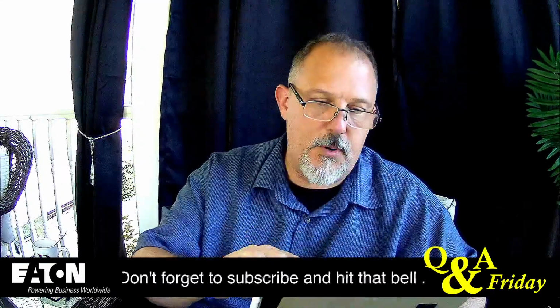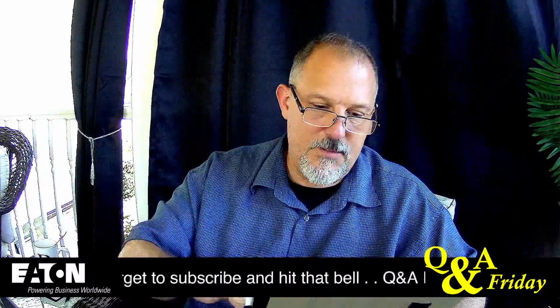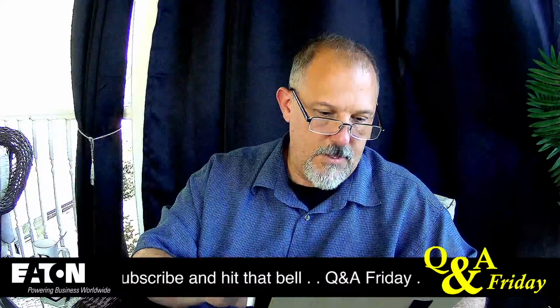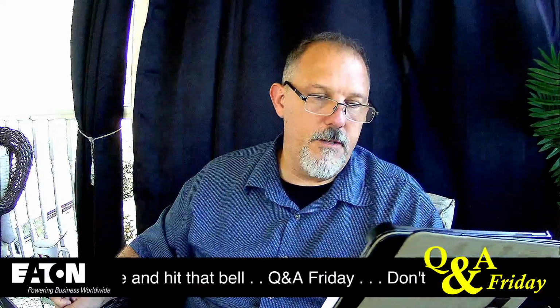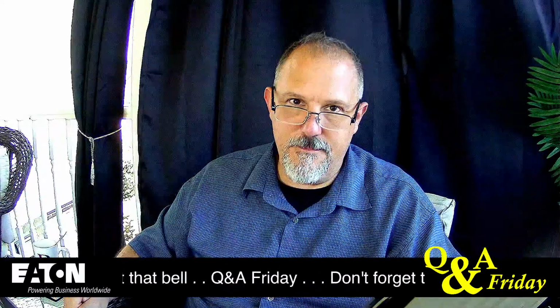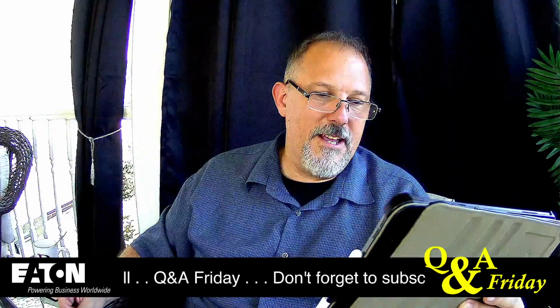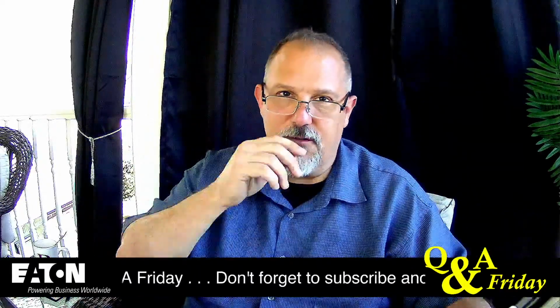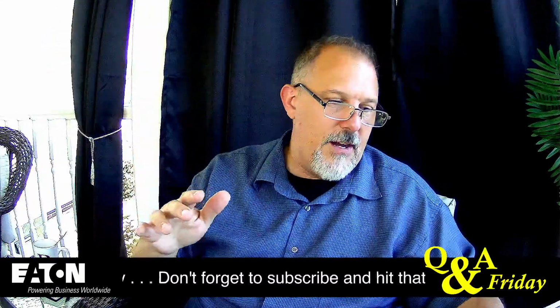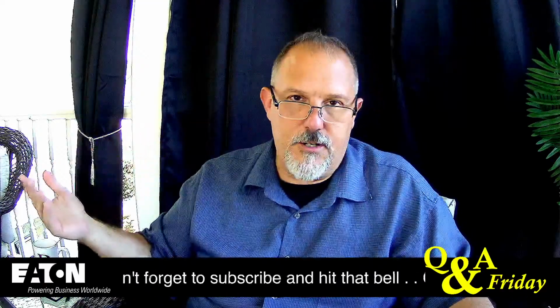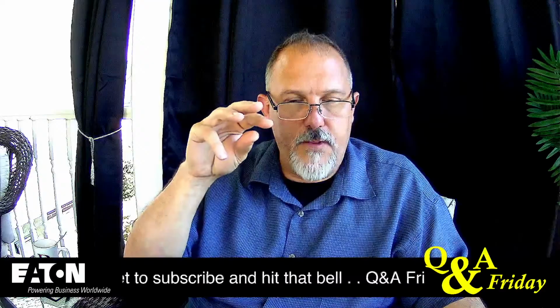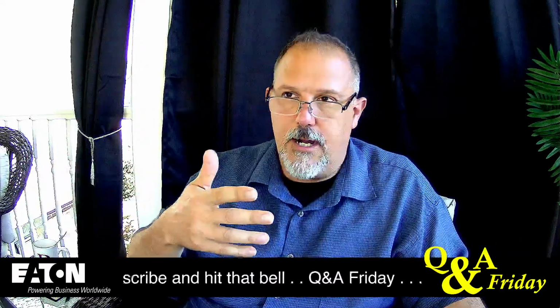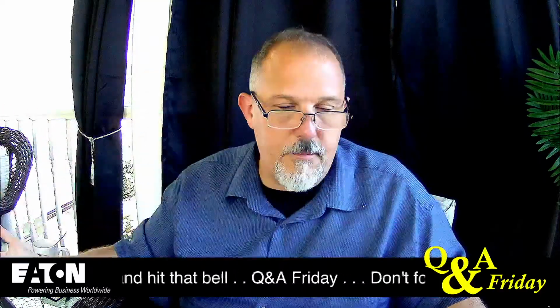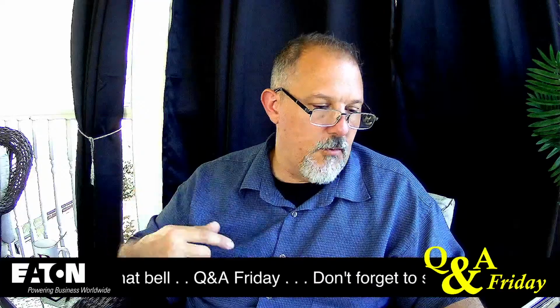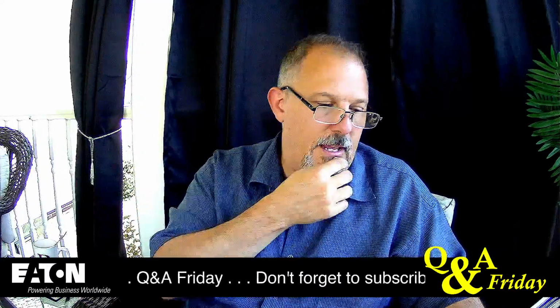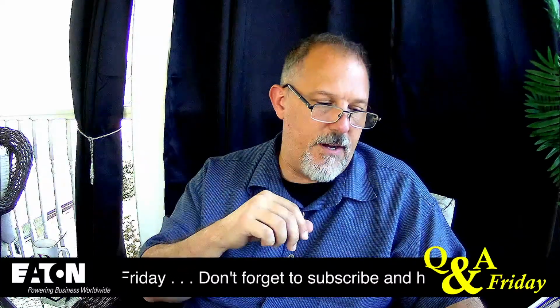And so based upon the discussion, where is it? Is it here? All right. If a service is fed with 3-phase, 3-wire load, how do you get the effective ground fault current path? So they wanted an effective ground fault current path coming from the service and saying, look, it's a 3-phase load. I don't need a grounded conductor. I don't need a neutral because it's a 3-phase load. There's no line to neutral loads there. So say it's a motor, right? And I need an A, B, and C, and I don't need a neutral. So where do I get my ground fault current path? And they said, do you run a neutral out to that main disconnect for bonding of the equipment ground or not? And they showed a diagram from the NEC.